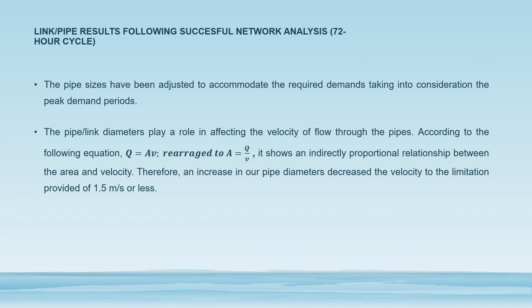Pipe or link results following the successful network analysis of the 72-hour cycle: the pipe sizes have been adjusted to accommodate the required demands, taking into consideration the peak demand period. The pipe diameter plays a huge role in affecting the velocity of flow through the pipes, using the equation: flow equals area times velocity. This equation shows an inversely proportional relationship between the area and the velocity. Therefore, an increase in pipe diameters decreases the velocity to the limit of 1.5 meters per second or less.